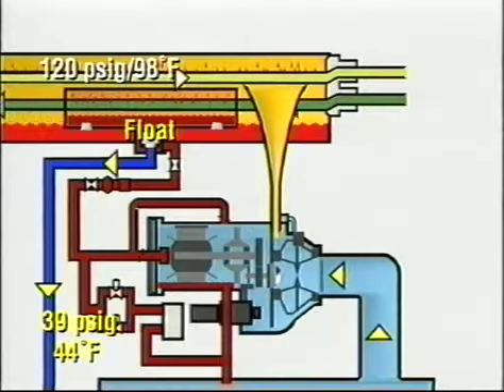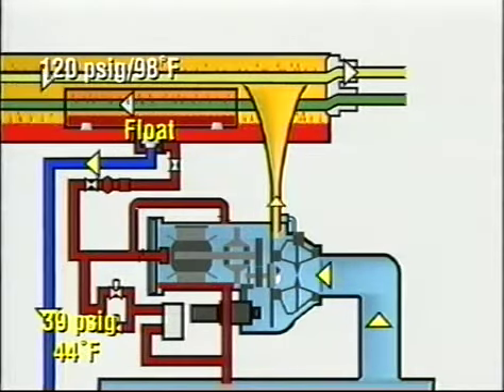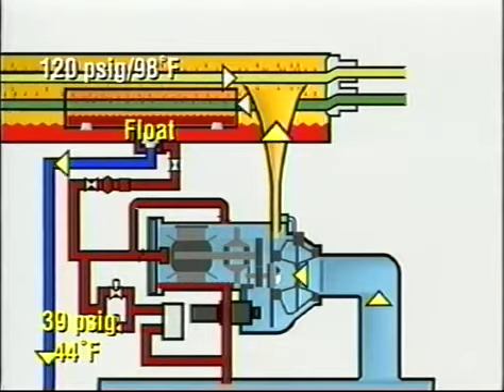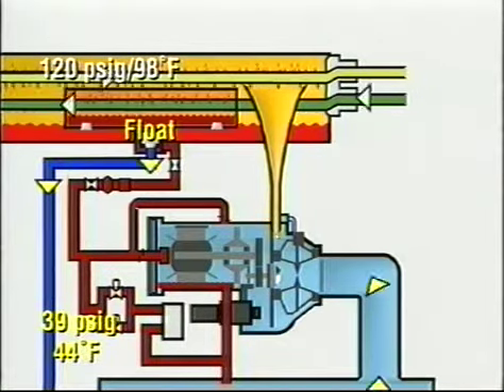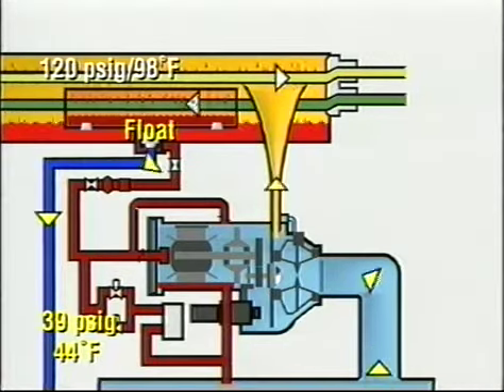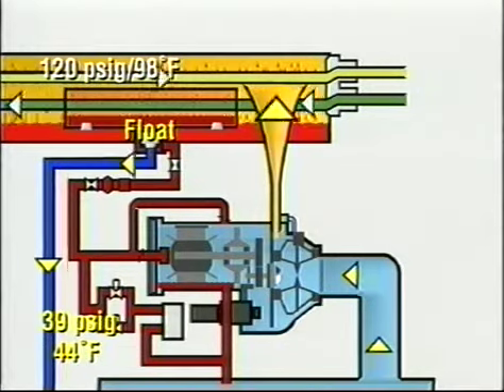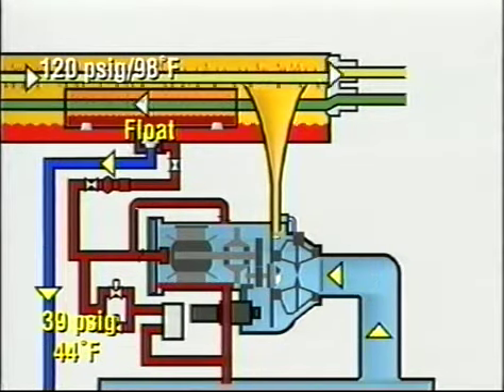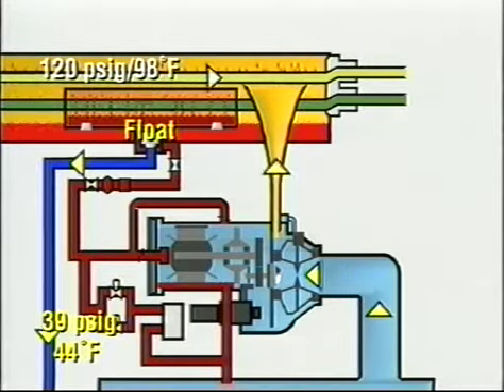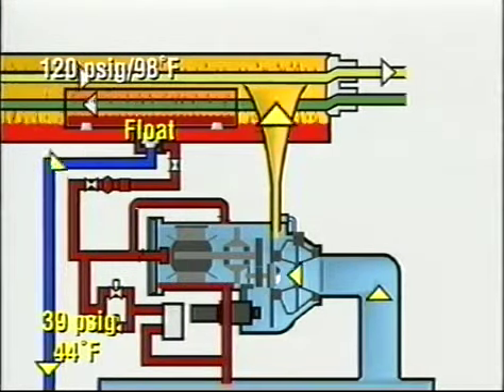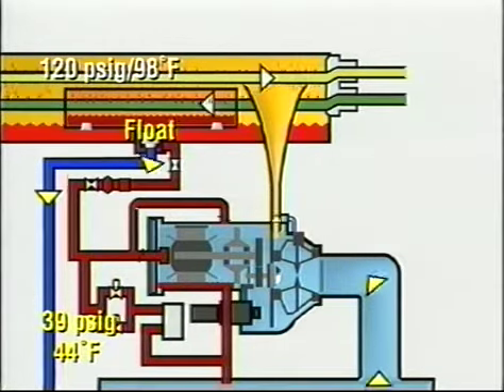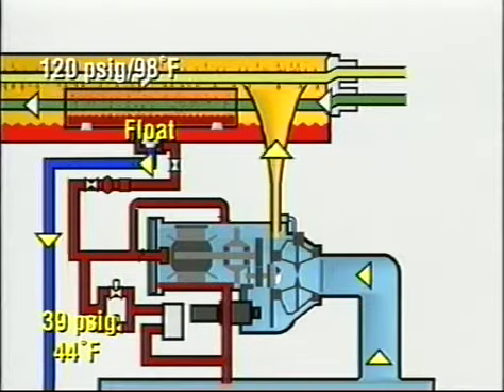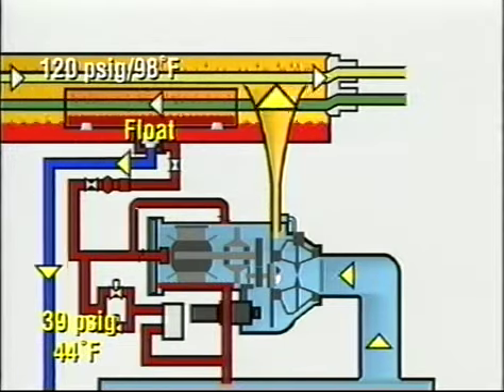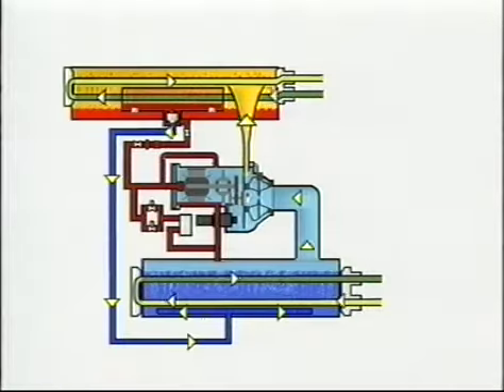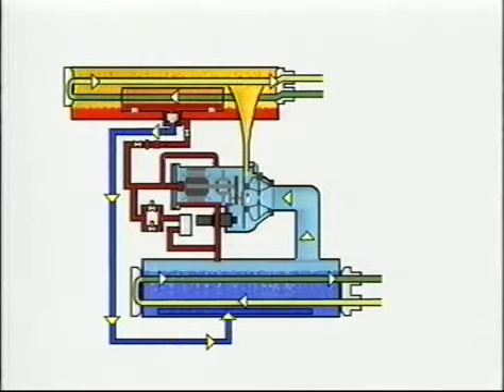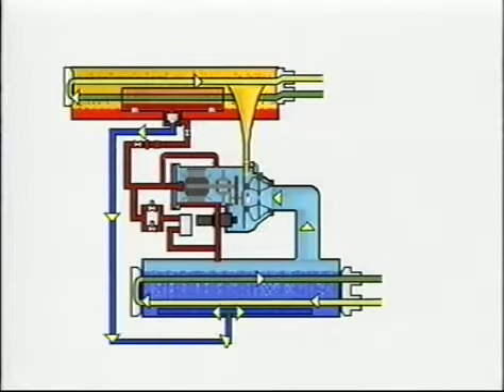The float maintains a refrigerant level in the float chamber, which provides a positive liquid seal and prevents condenser vapor from blowing directly into the evaporator. When the liquid passes through the metering device, some of it flashes to a vapor in the lower pressure on the evaporator side. In flashing, it removes heat from the remaining liquid, lowering its temperature to 44 degrees Fahrenheit. The cold liquid then flows into the evaporator shell, where the cycle begins again.